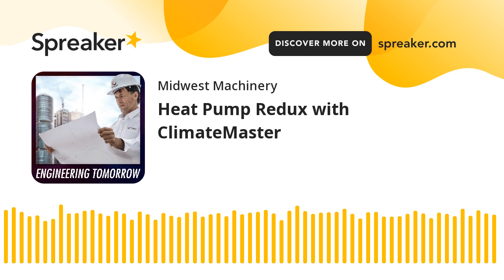Did you know water has 3,200 times more specific heat capacity than air? Now, what does this mean to me? Well, I'll tell you. It means two things for me in the water source heat pump systems. Number one, I can move as much cooling in water in a 2-inch piece of pipe as I can with air in a 24-inch square duct.